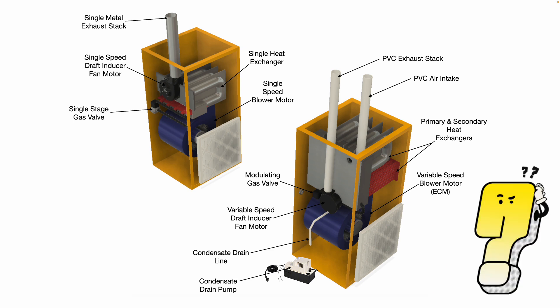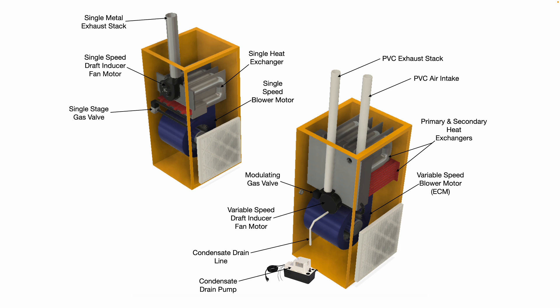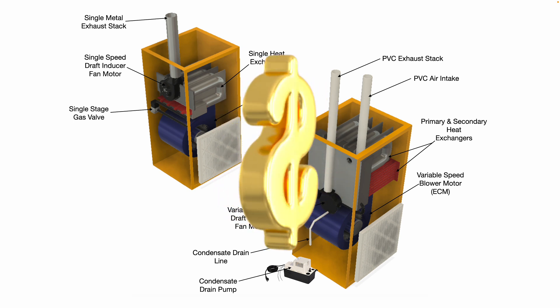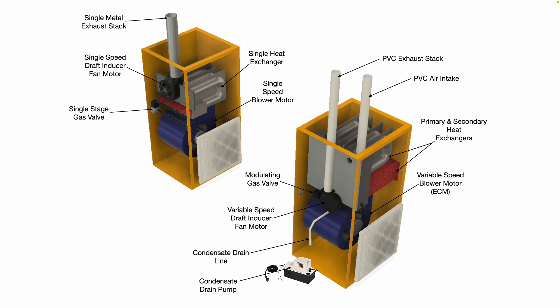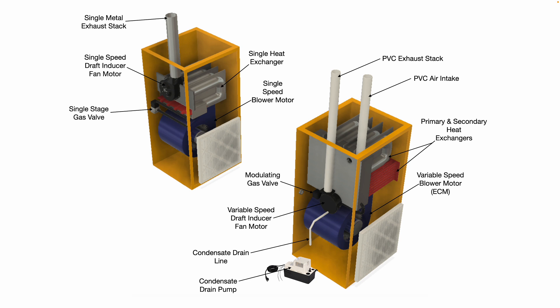Now if you're thinking about upgrading or replacing your old standard efficiency furnace with a high efficiency furnace, here are some things to consider. They are usually more expensive upfront to purchase and install — they have more components, including a second heat exchanger and multiple pressure switches instead of just one. Routing the PVC exhaust stack and PVC air intake is an additional cost, and depending on your local authority and building code, that's an additional penetration in your roof or the side of your building — more expense, more complication.